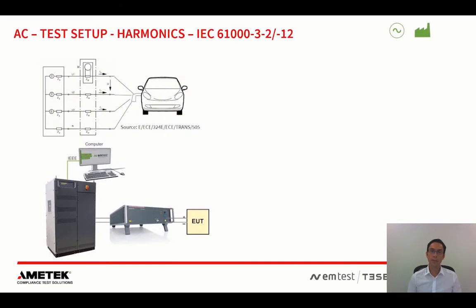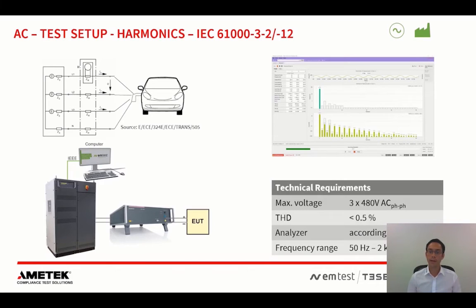The first test I want to start with is the harmonics test. This is defined in IEC 61000-3-2 and -12. As you can see on the top left, that's the test setup. Basically we need a three-phase or single-phase AC source that provides a very clean signal to the test object, which in this case is the car in charging mode. What is shown in the middle there is the measurement device. It's typically a power analyzer that is capable of measuring harmonic currents, and usually also harmonic voltages. So it measures the harmonic current emission generated by the car in charging mode.